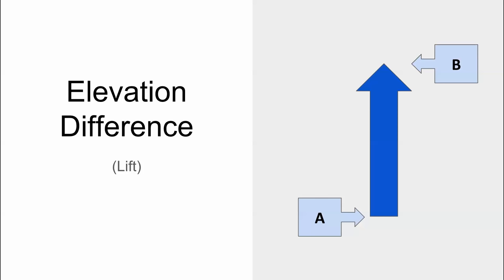Regardless of if the pump is a hundred feet away from the discharge location, a one foot rise is a one foot rise. It's important to realize that when calculating the lift or elevation, you're only taking into account the height differential between where the pump sits and where the discharge location is going to be.